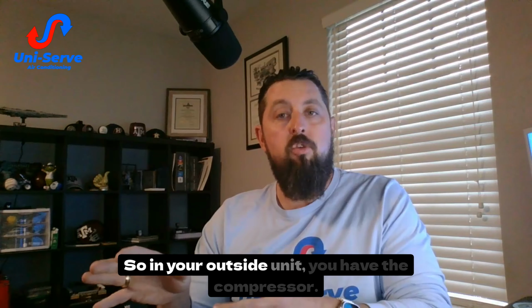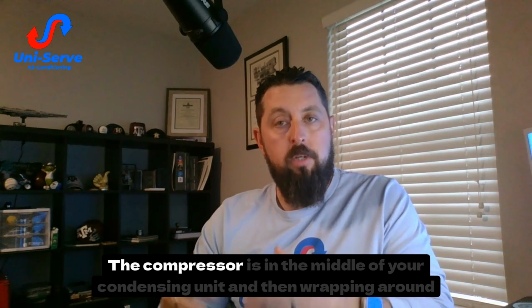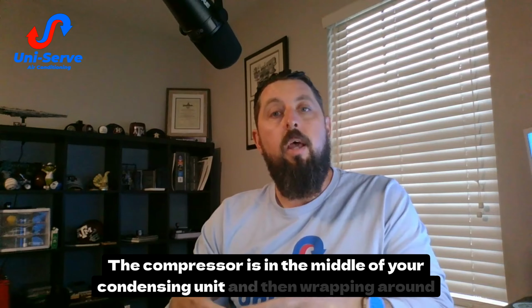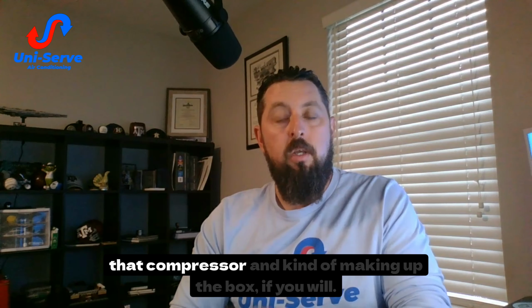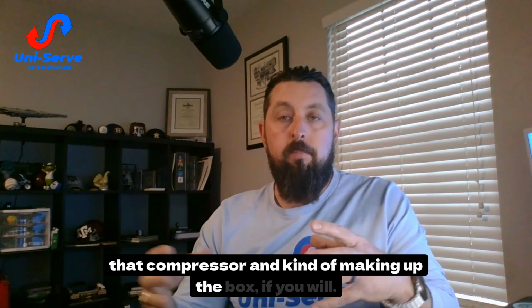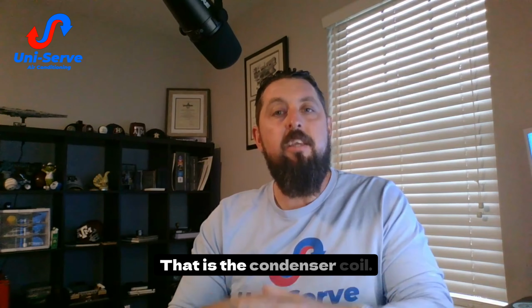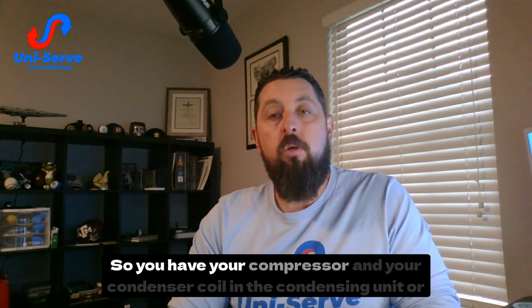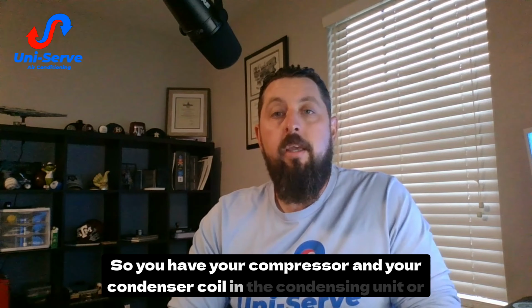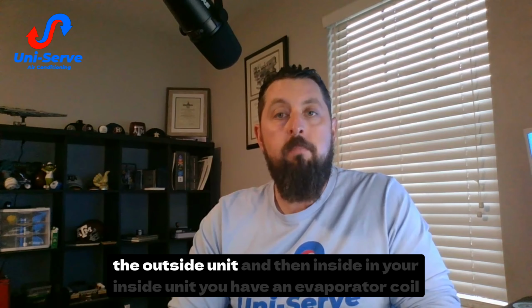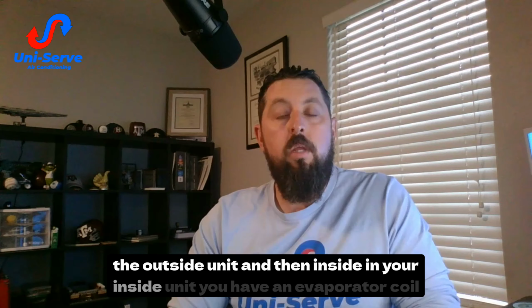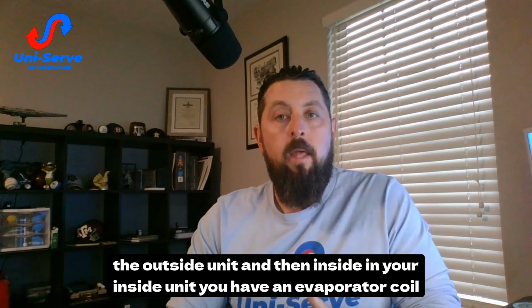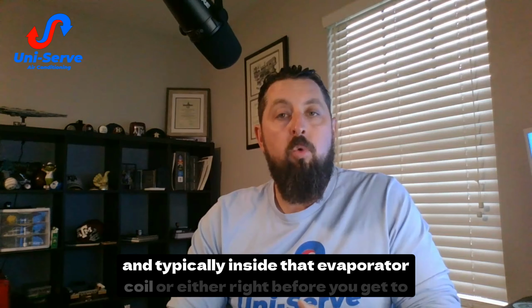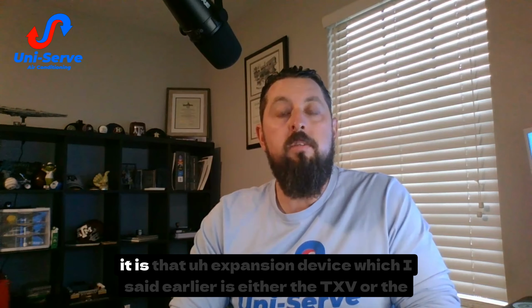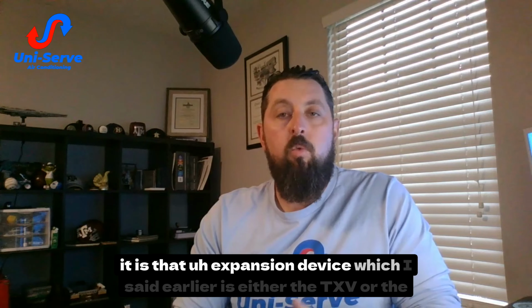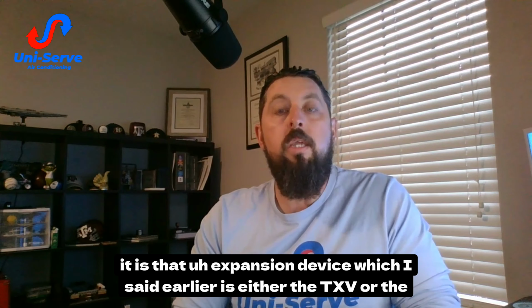All right, so just kind of walking you through that. In your outside unit, you have the compressor. The compressor is in the middle of your condensing unit. And then wrapping around that compressor and kind of making up the box, if you will, is the condenser coil. Okay, so you have your compressor and your condenser coil in the condensing unit or the outside unit. And then inside, in your inside unit, you have an evaporator coil. And typically inside that evaporator coil, or right before you get to it, is that expansion device, which I said earlier is either the TXV or the EEV.